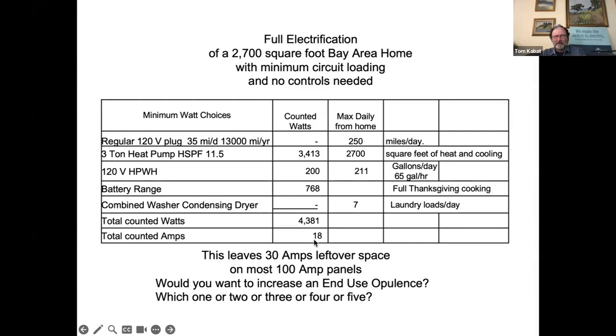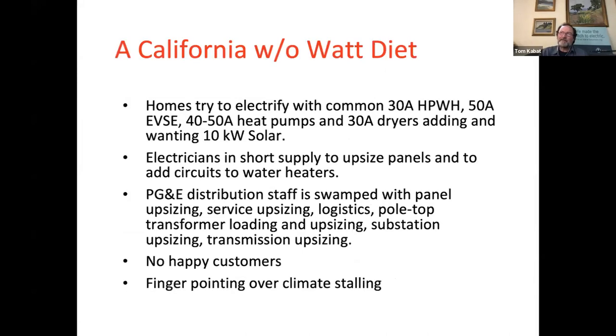Anyway, summing that all up was only 18 amps counted on the panel. So this might leave, say, 30 amps left over on most 100 amp panels. And then you could ask yourself, well, where would I want any additional opulence in one of my end uses? Which one or two or three or five would I want to increase above that if I had leftover space? So that's an approach of starting efficient and small and right-sized, and then just saying, okay, I know I can get there.